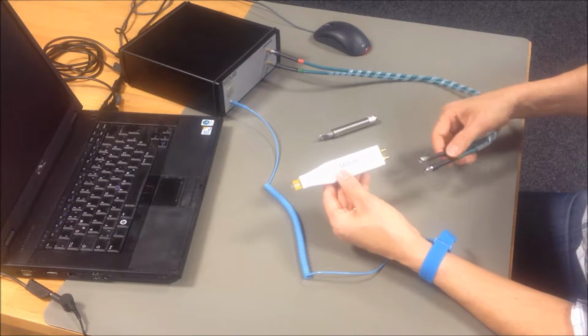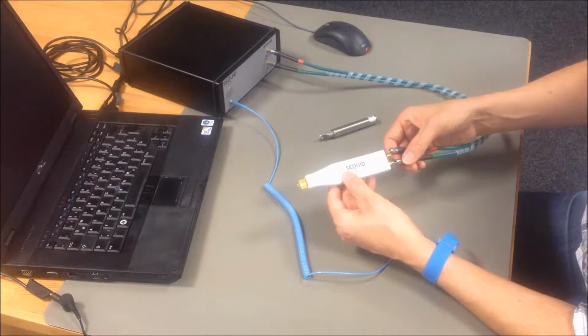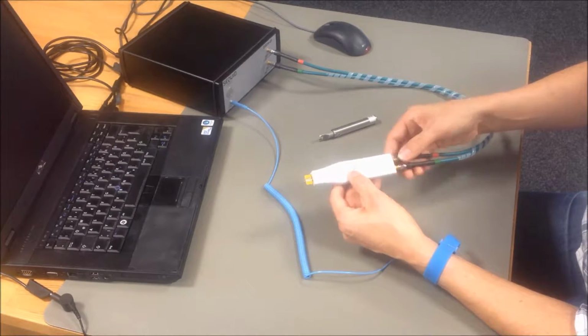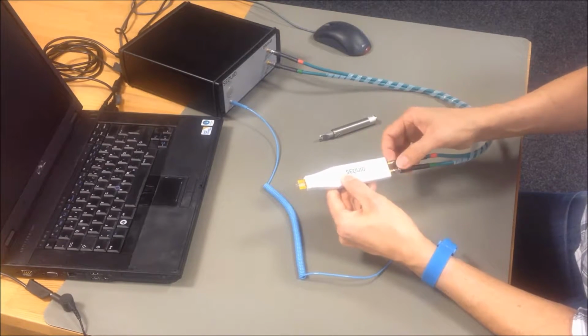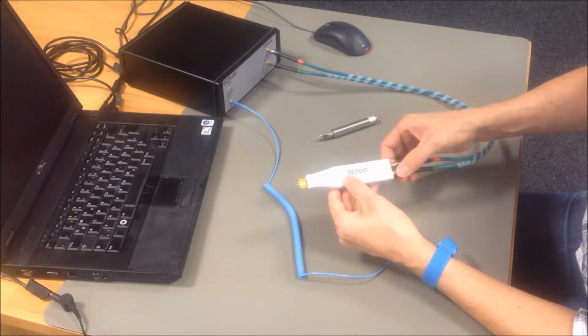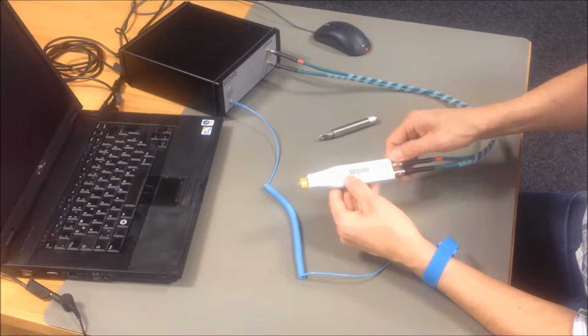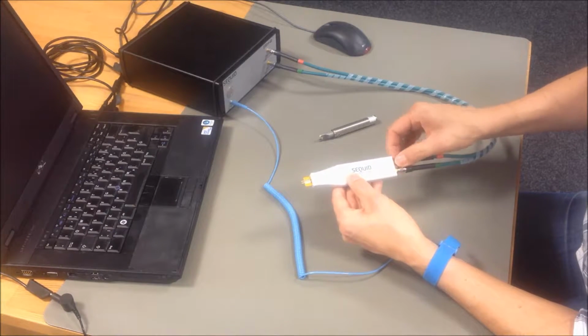Next step is to connect the differential TDR probe. Again, tighten the SMA screws and fix them afterwards with a torque wrench.